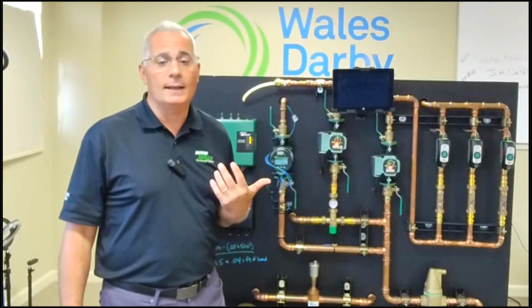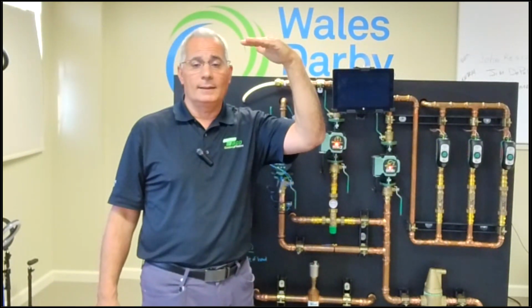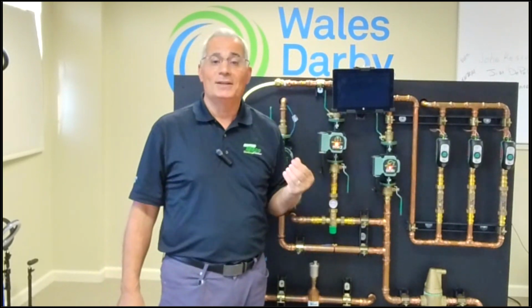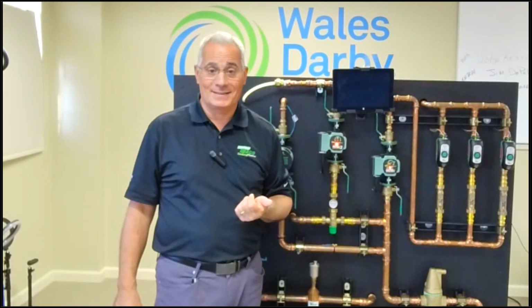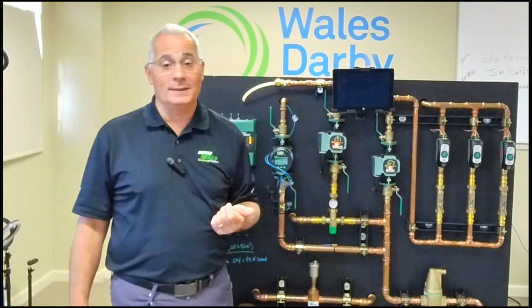But I could use this 0018e in the fixed speed mode. Let's say I have a radiant system and it's not working properly, and I'm really not sure if it's being pumped properly. And it's kind of hard to see what was done. Maybe this tubing is in concrete. We have ways of guesstimating what the centers are so we can figure out loop lengths and things of that nature, but sometimes it's really hard. If I put this 0018E on the radiant side and I put it into that blue mode, I can turn the system on and the pump will go right to where it would be functioning based on that system layout. So then it would tell me what the GPM and head is. So that's really a cool little diagnostic feature.